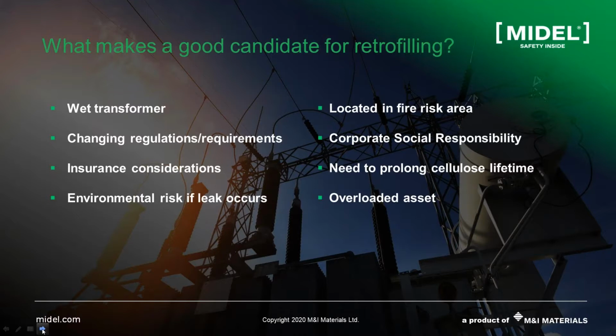MIDEL offers a more flexible and safe overload profile without greatly reducing life, as it would in mineral oil. It's common knowledge that an increase in temperature of around 6 degrees in mineral oil could reduce the life of the transformer by half. If we consider the IEC standards, with MIDEL we can go 15 degrees hotter for the same life. That's a huge benefit.